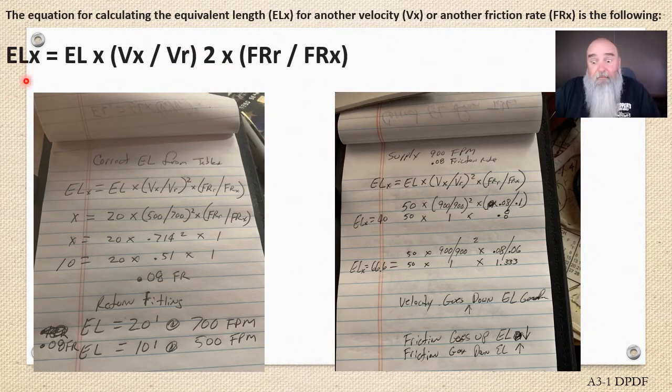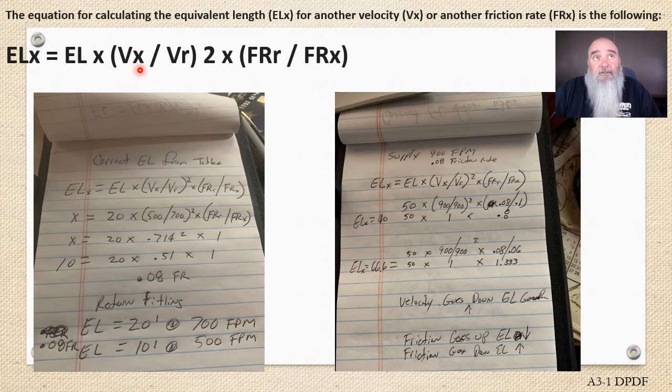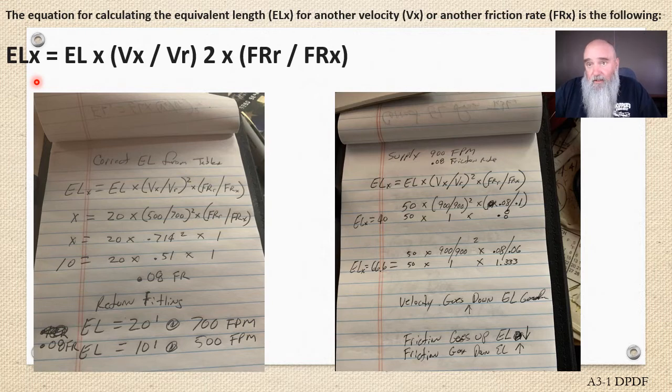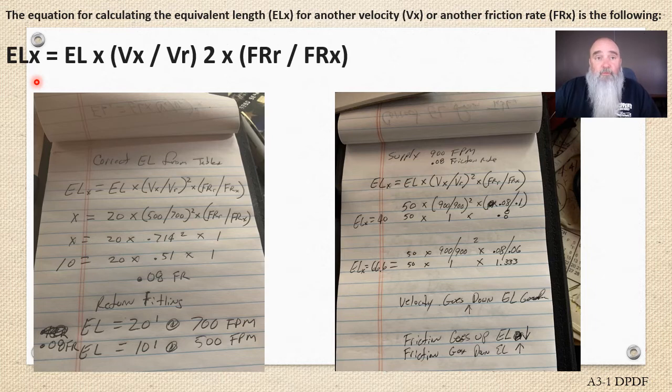So this is the math, and I'm going to call it the heavy math because any math with letters to me is heavy. But there is a process in Manual D that they don't highlight, but essentially what it is giving us the ability to do is to correct for those equivalent lengths, where those pressure drops as they will exist with a different velocity.